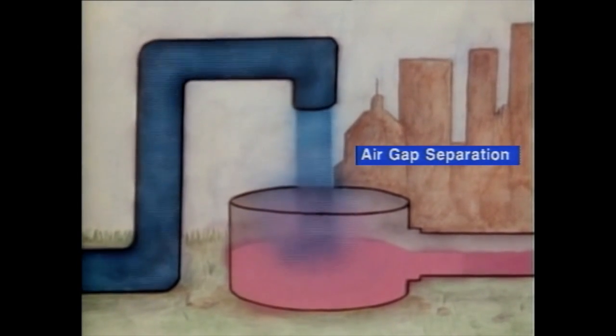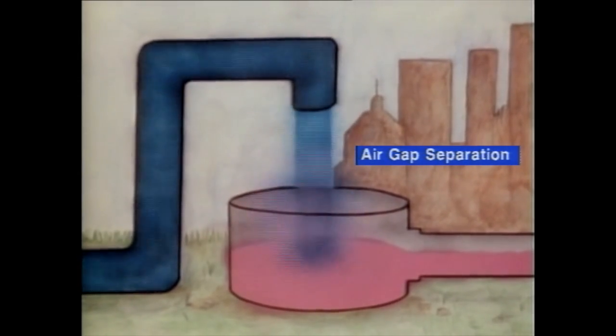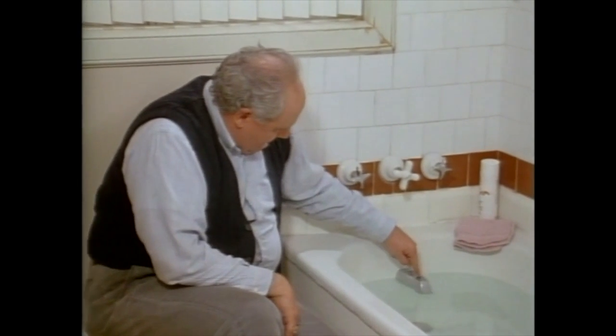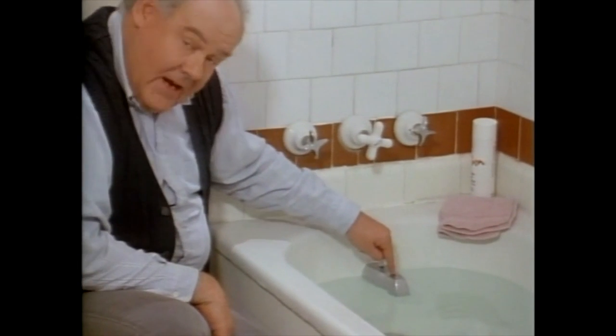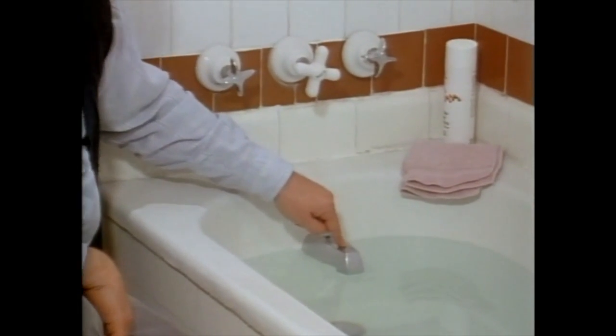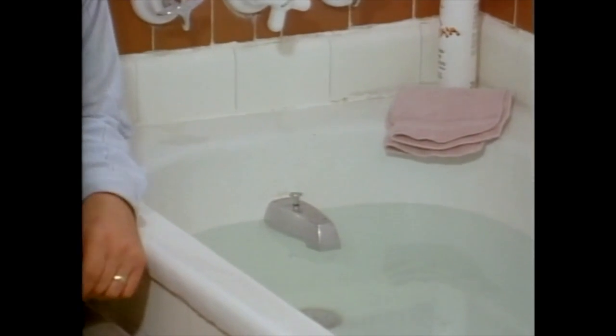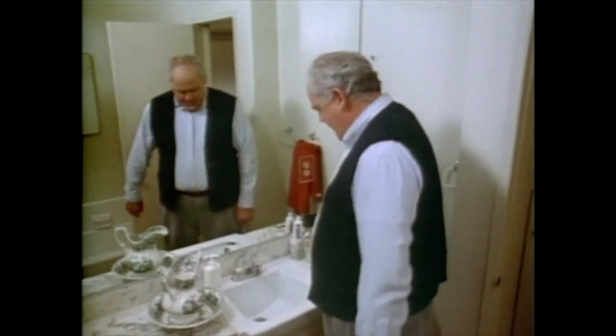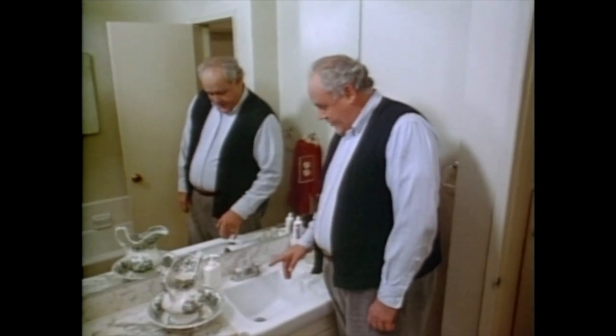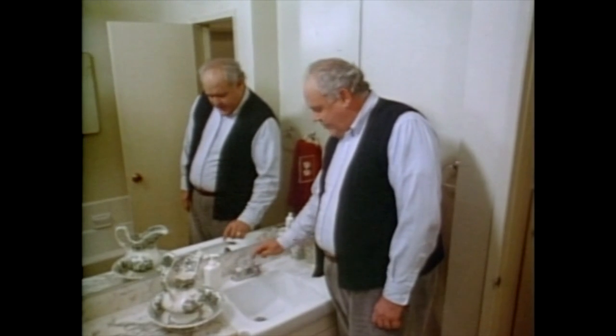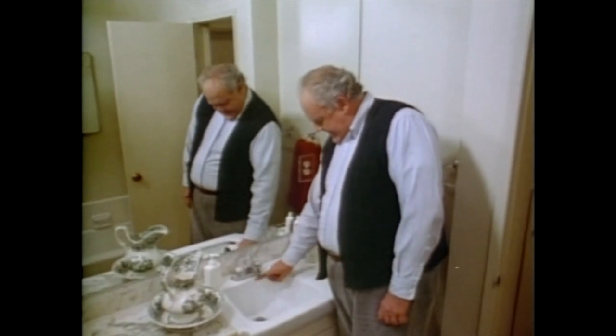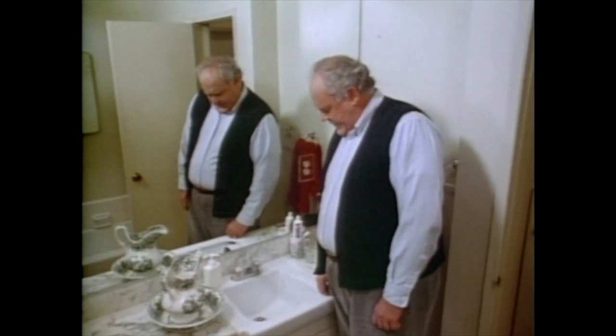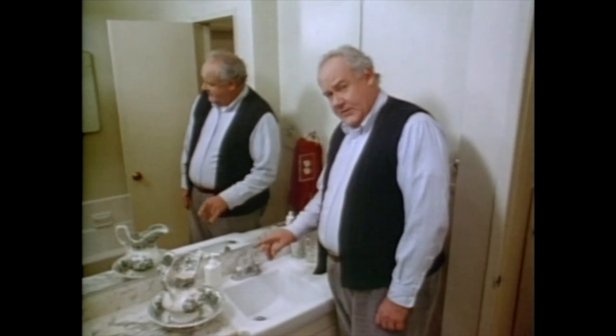Air gaps are simple, effective, and you see them applied every day. Remember that old-fashioned bathroom? Look what happens when the bathtub is filled up — this water, now in direct contact with the public water supply, is also in direct contact with the drain, and we all know where that goes: the sewer. We've just cross-connected the sewer with the public water supply. If you fill a modern wash basin all the way up, the water level never reaches the nozzle of the faucet — that's an air gap. Plumbing codes have mandated that every sink must have this air gap.